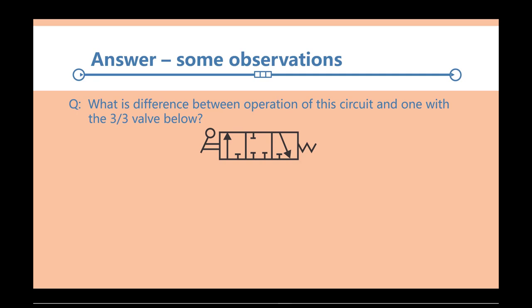Now let's look at another scenario here, or a different type of valve, and this is a three by three valve. What I mean by that, excuse me, if you count the connections, of course, they're three, just like we had before, but we have three envelopes now instead of two. We have the two envelopes that we had before, and they're shown on the ends, and actually the retract envelope is the default envelope again, and then we have a blocked envelope in the middle.